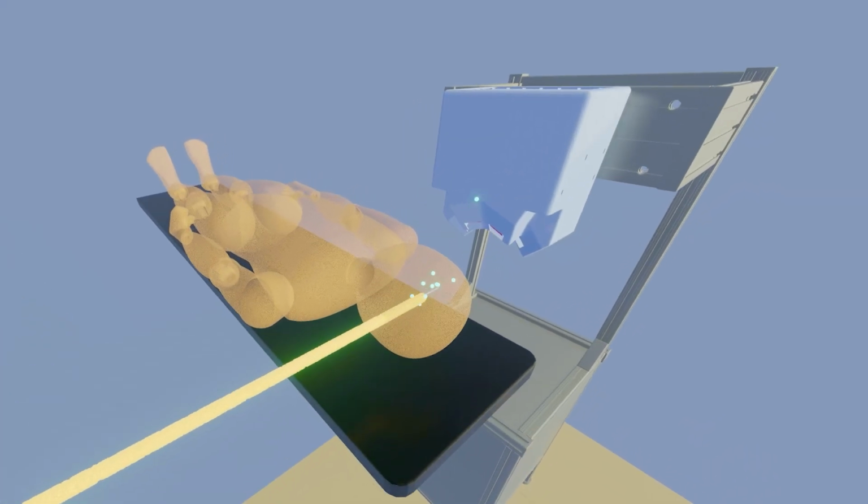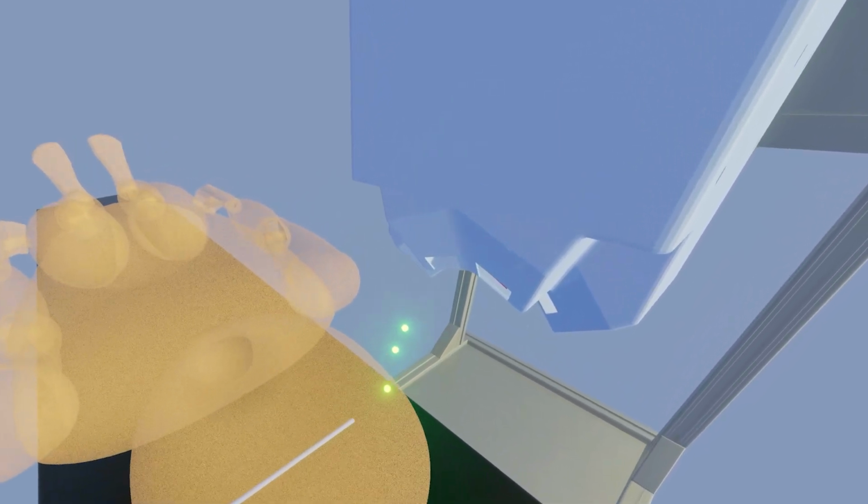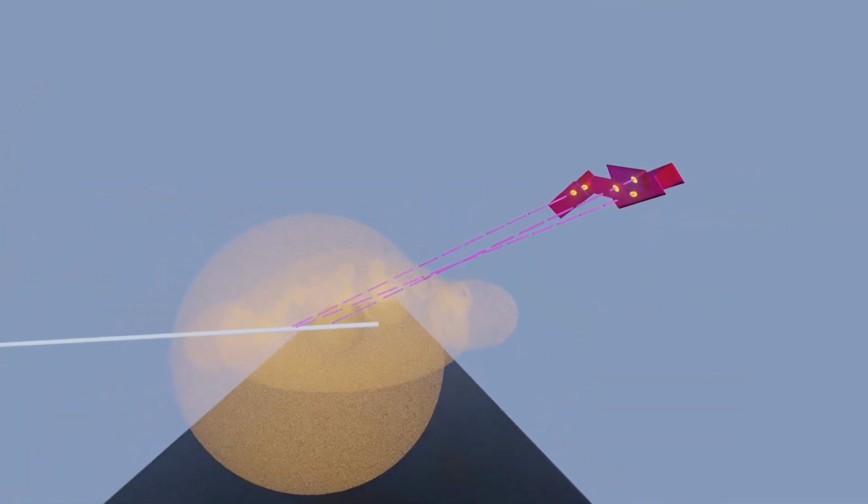Jan, in the introduction, I referred to the system as a navigation for ion beam irradiation. In what sense does it serve as navigation? Actually, I would not say navigation, because the plan for irradiation already exists before the device is used. It is basically verifying that everything is going according to plan, that the original model of the patient with the location of the tumor has not changed during the therapeutic procedure lasting several weeks. And it is very often not true. So there are, of course, changes. The reason of the therapy is to cause the changes, because the aim is to remove or to kill the tumor. So the changes are logical.